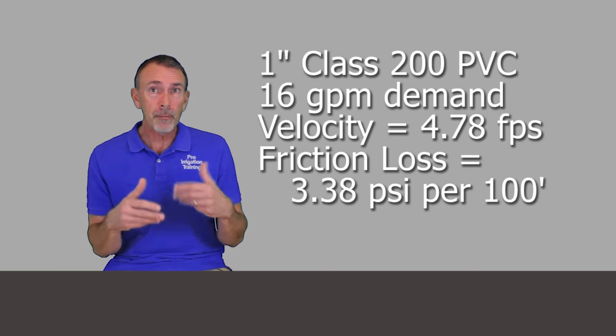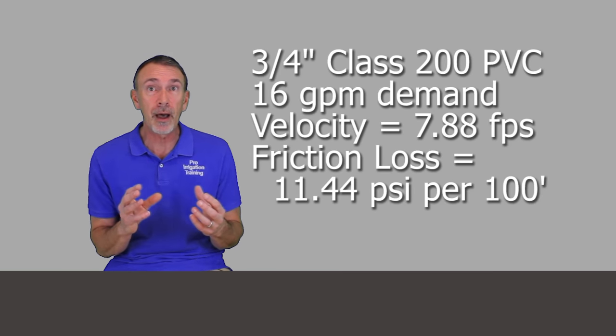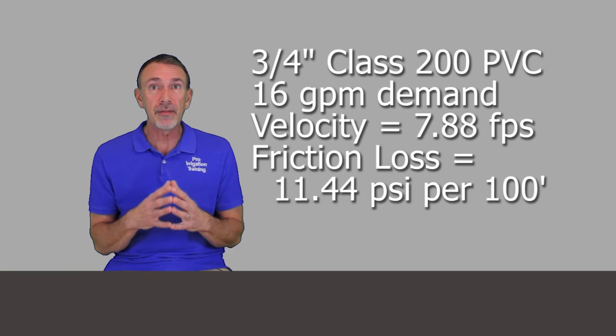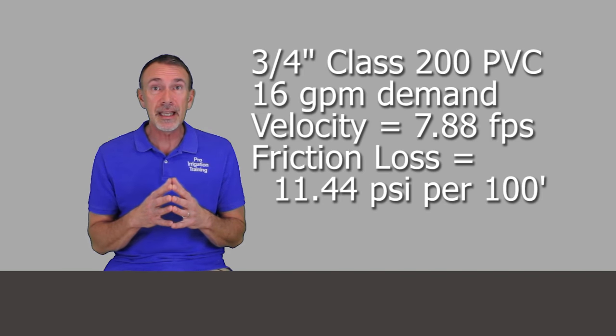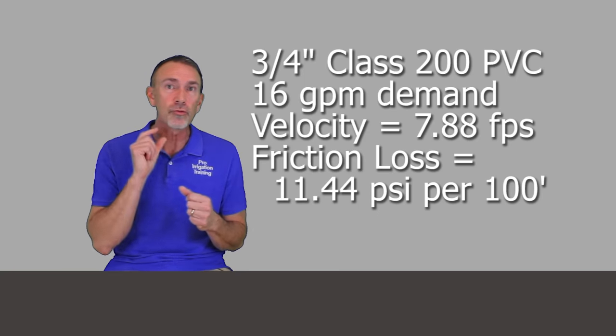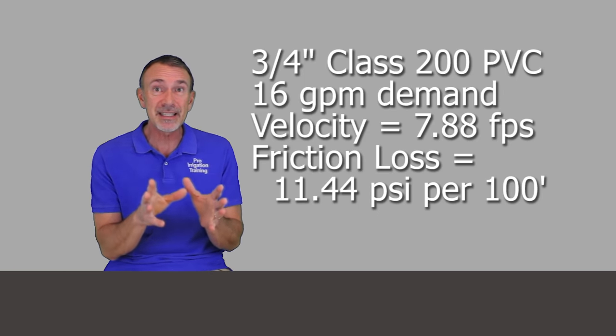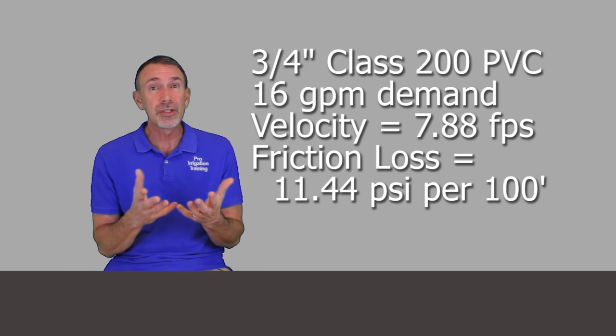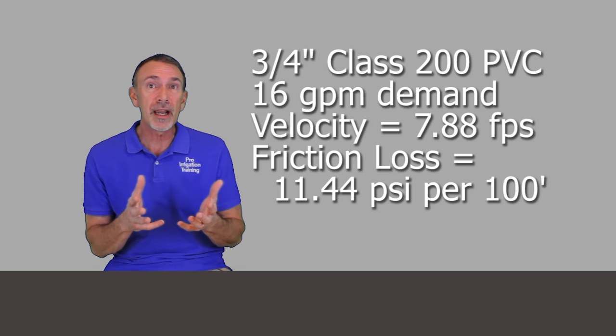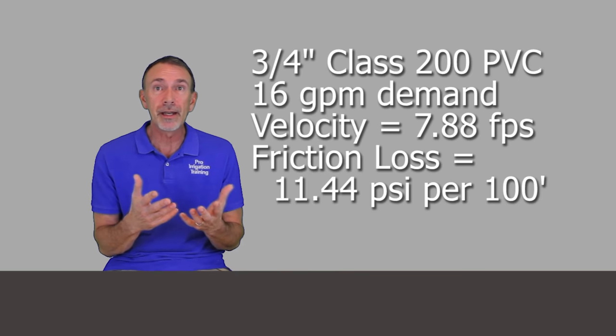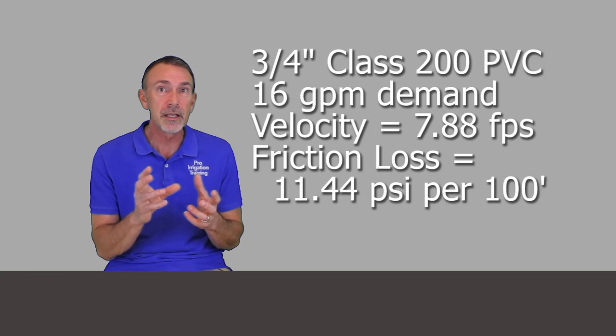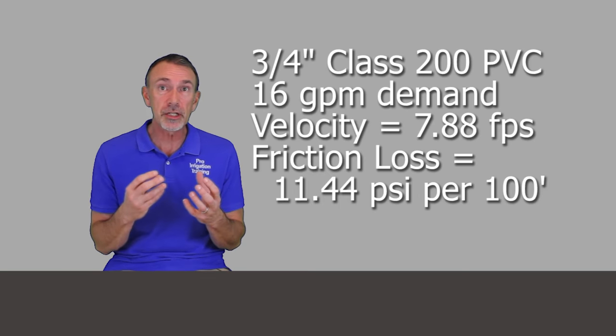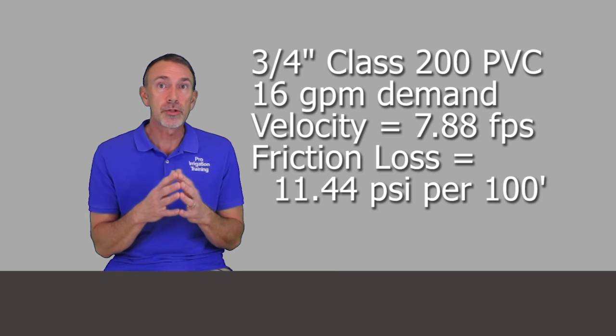Let's say we took that one inch pipe and replaced it with three-quarter inch pipe thinking that we were adding pressure to it. For the same 16 gallon per minute demand our velocity is now at 7.88 feet per second. That water is really moving through the pipe trying to supply that 16 gallon per minute demand. It may not supply it all because three-quarter inch pipe is rated for up to 10 gallon per minute flow and above that you're getting into those really high delivery rates.